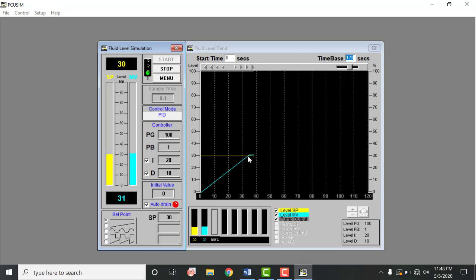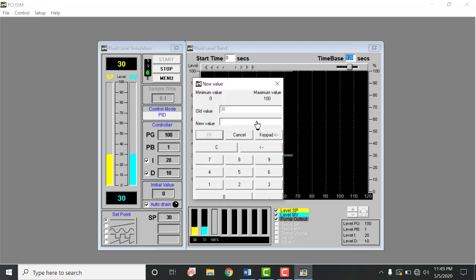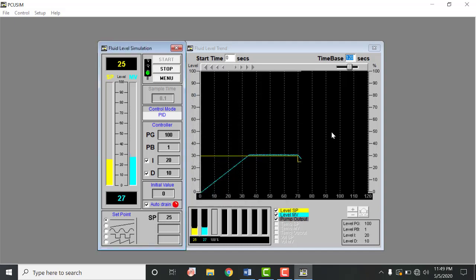So now you can see that after slightly exceeding this value, this auto drain is showing on-off behavior just to achieve this 30 liters per minute. But you can see that we are losing our power, because right now our pump is still working at its 100%. Okay, now let the set point value be reduced to 25. Now you can see that the time of the auto drain pump is increased, and this is again sustained at that 25 liters per minute.